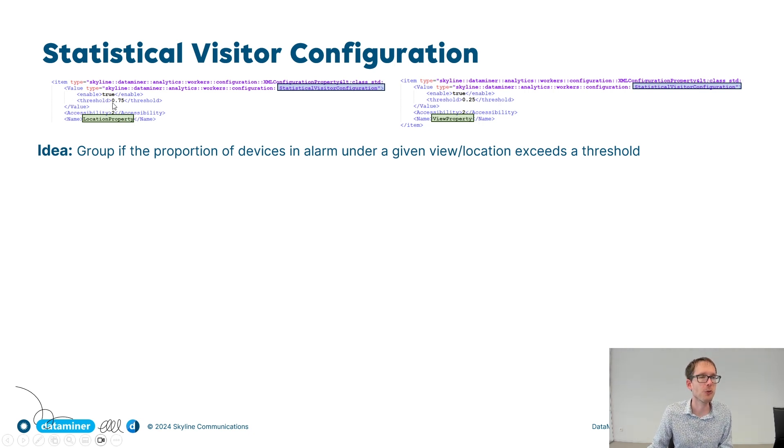If you set this threshold to 0.75, then we will group alarms on devices at the same location, but only if at least 75% of the devices in that location have problems. Else, we do not group.